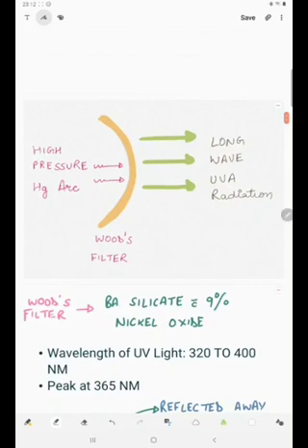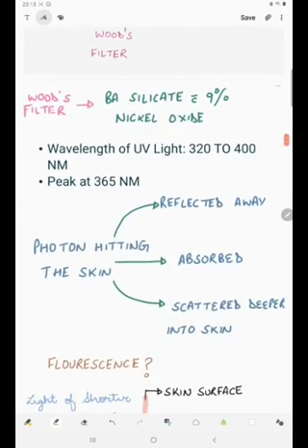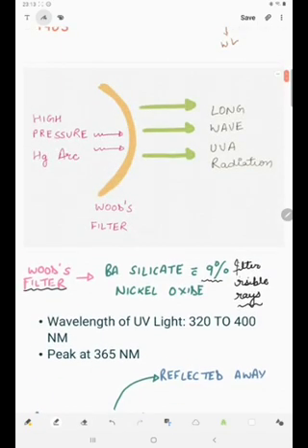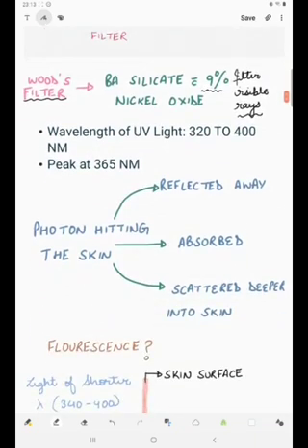We have a high pressure mercury arc. A high pressure mercury arc will emit some radiation that will pass through a Wood's filter and some long wave UV radiation will be emitted further. Wood's filter is made up of barium silicate with 9% nickel oxide. It will filter all the visible rays. The UVA radiation that is emitted by the Wood's filter will be invisible, not visible to the naked eye. The wavelength of UV light is 320 to 400 nanometers and it will peak at 365 nanometers.